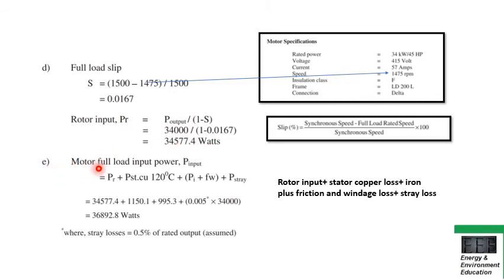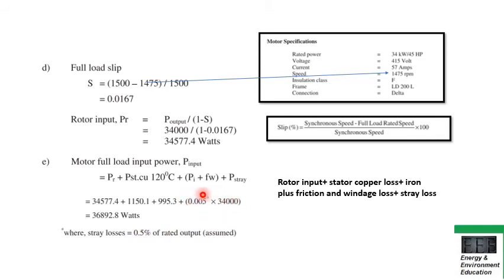For Part E — motor full load input power — you add: rotor input, plus stator copper loss, plus iron and friction and windage losses, plus stray losses. Stray losses are 0.5% of rated output (34,000 W). All the previous calculated values are summed together, giving motor full load input power equal to 36,892.8 W. All five parts are interlinked — each earlier result feeds into the next calculation.